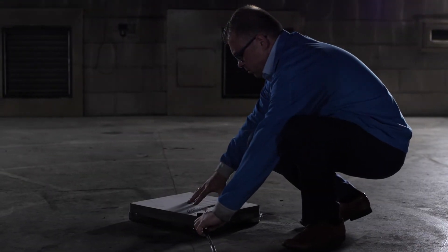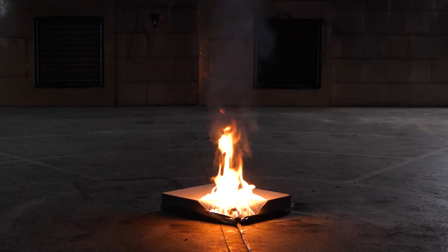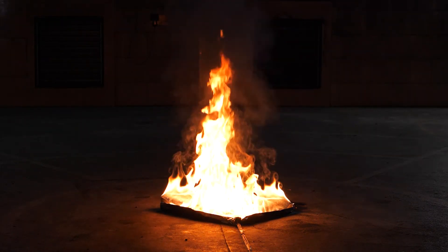To recreate these tests in the Apollo fire test room, I visited UL's fire lab in Chicago to gain a better understanding of the fire test setup and combustion materials used. I also imported the same grill oven and hamburger baking tray from the USA as UL has. Before final product submission to UL 268 edition 7, we also tested detector prototypes in UL's fire lab to get exactly the same compliant fire results.